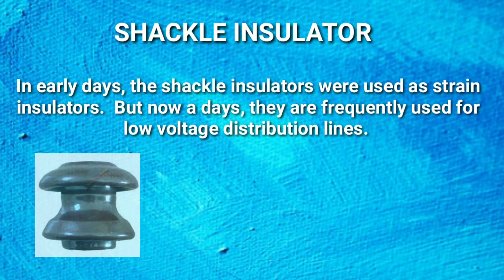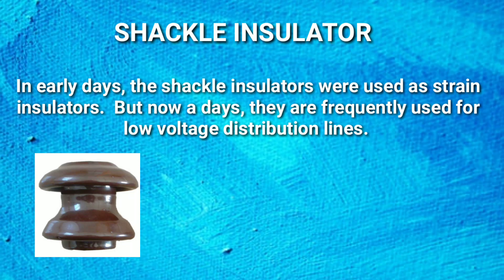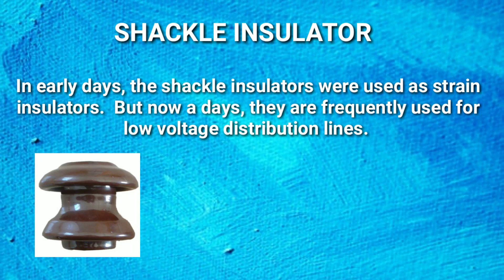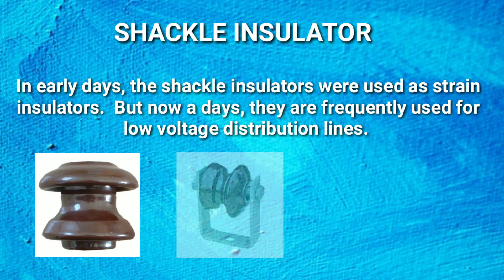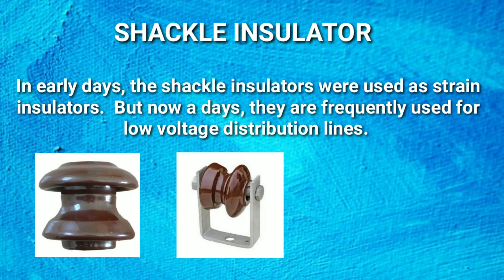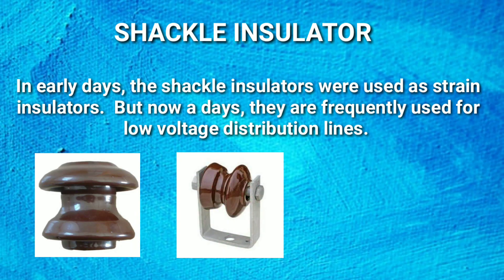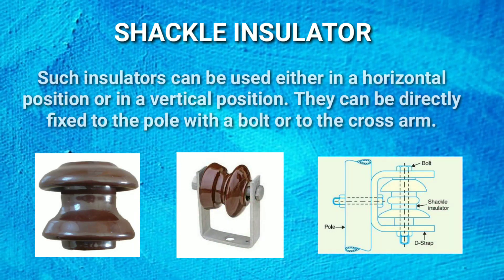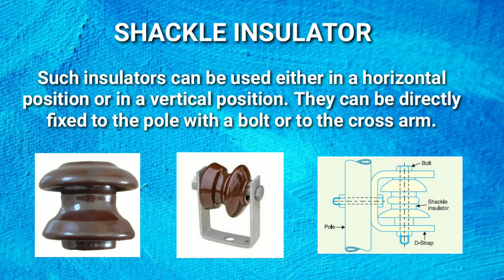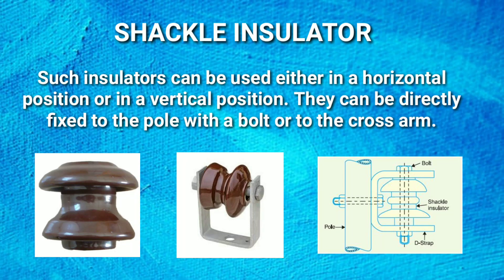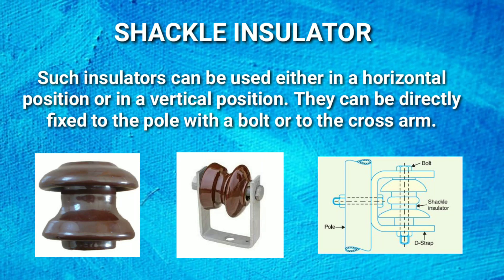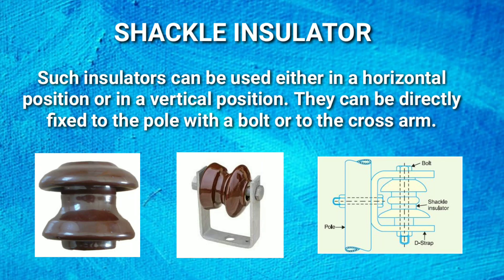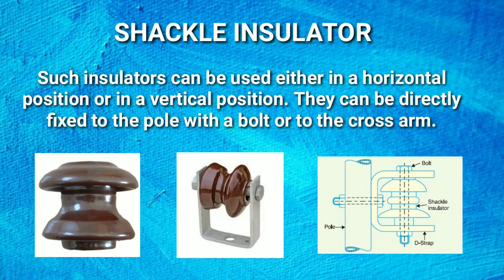Shackle insulator: in early days, the shackle insulators were used as strain insulators. But nowadays, they are frequently used for low voltage distribution lines. Such insulators can be used either in a horizontal position or in a vertical position. They can be directly fixed to the pole with a bolt or to the cross arm.